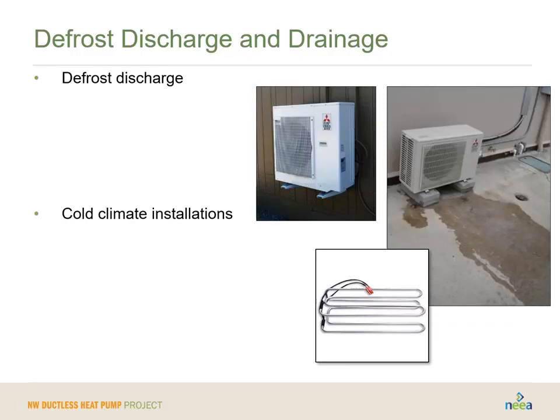The lower picture is actually a pan heater that is really another specific element often used in defrost modes. These can be ordered with the equipment or they can be purchased separately. We only recommend them when you're installing cold climate ductless heat pumps in a colder climate. The reason why is they do use extra energy in order to work. We also want to make sure that the way they're controlled is to only come on during defrost cycles. Now that should be a standard for most pieces of equipment these days, but it's the kind of thing you're going to want to learn more about as you're going through manufacturer training, really understanding how the defrost mode works and what considerations need to be taken into account.